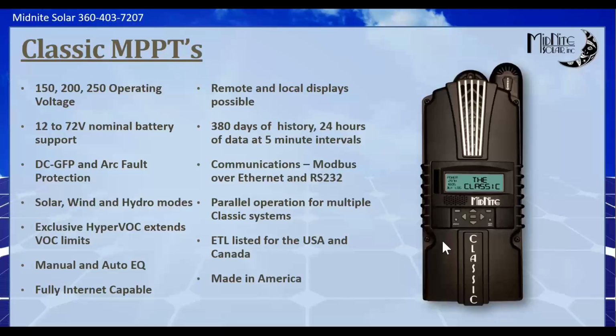But both of those models are available in 150, 200, or 250 volt operating voltages. That's your VOC, if you will. So if you've got an array that's at 200 volts VOC and it gets cold enough there where it rises to like 240 volts, then you'd use a Classic 250. The Classic 150 is the most powerful and the least expensive. Even today at 80 or 90,000 of these things out the door, a lot of people still think the 250 is more powerful because it's a bigger number, but it's actually less powerful into the battery. It just can handle a higher PV voltage.